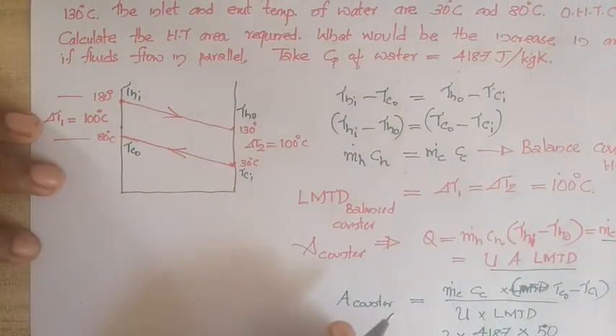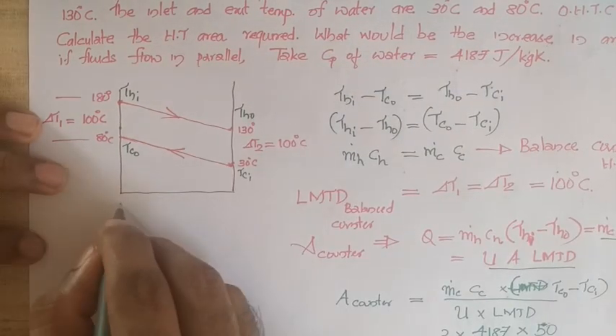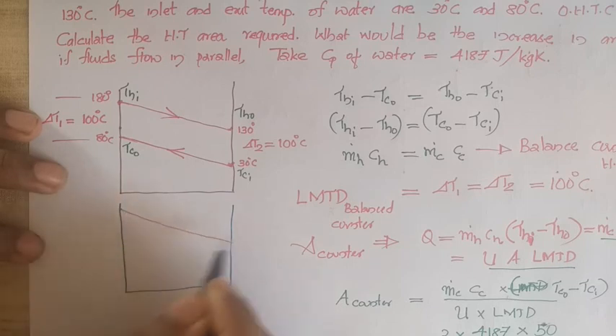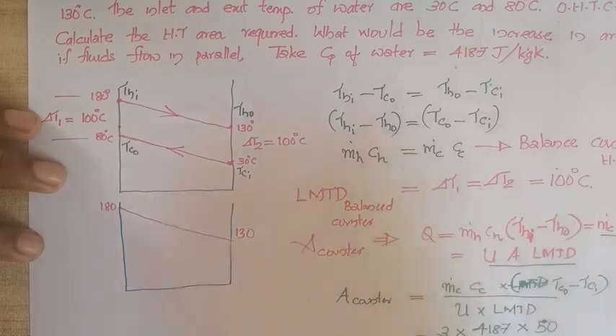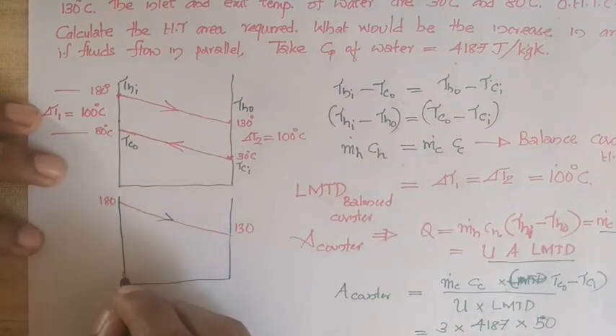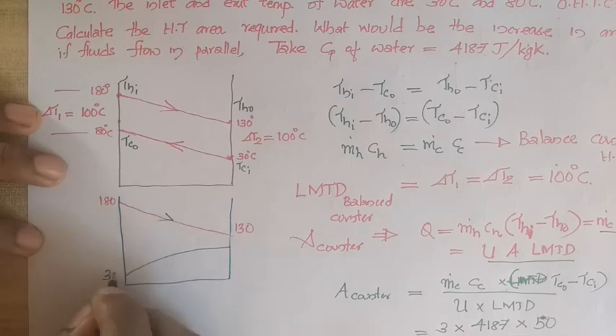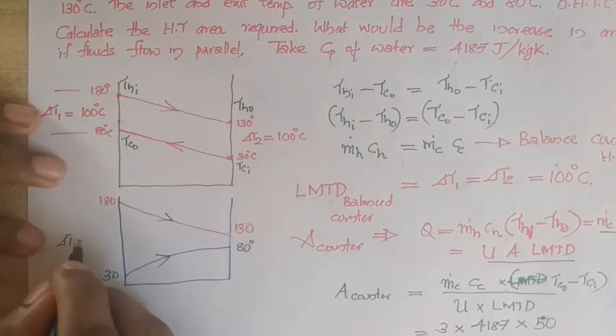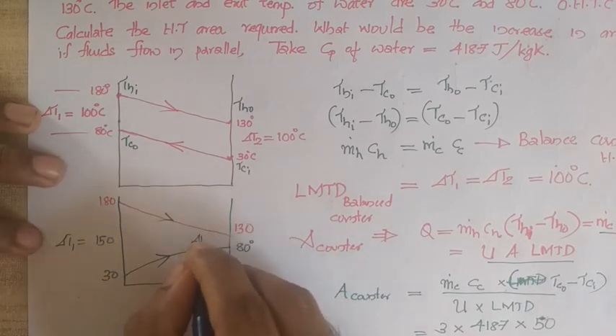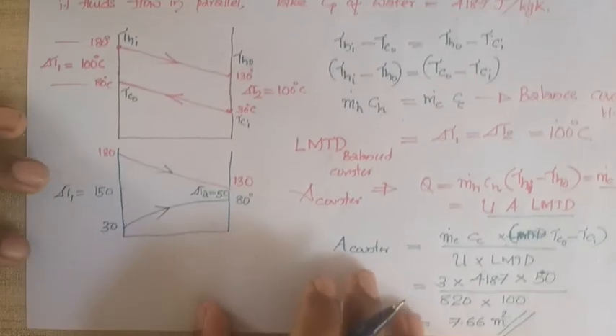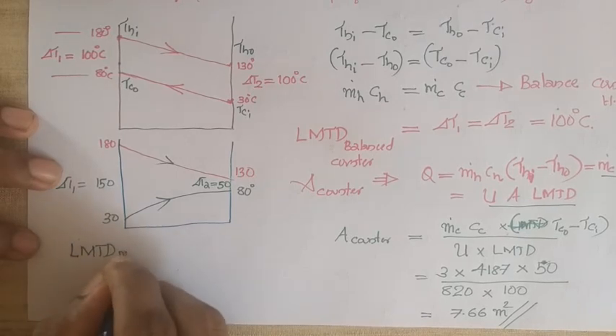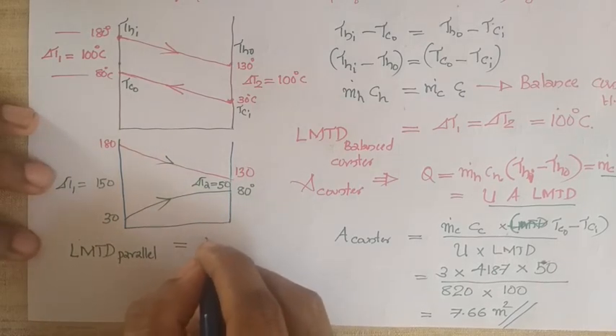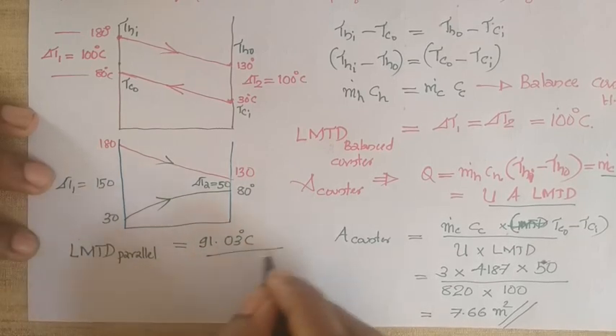The last part asks for the increase in area if the fluids flow in parallel. For parallel flow, both fluids move in the same direction: hot fluid from 180°C to 130°C and cold water from 30°C to 80°C. Here ΔT1 = 180 − 30 = 150°C and ΔT2 = 130 − 80 = 50°C. The LMTD for parallel flow is (150 − 50) / ln(150/50) = 91.03°C.